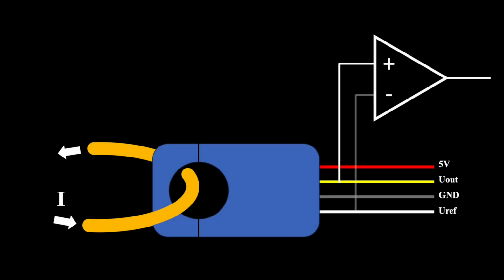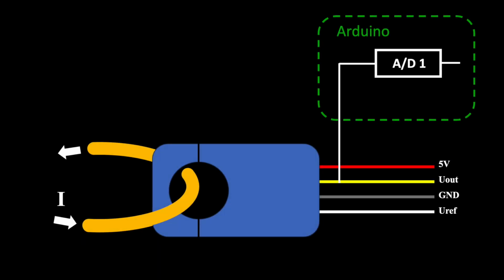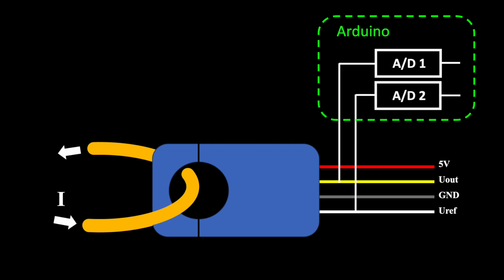Applying a differential measurement, we can eliminate the zero offset drift using the reference voltage output. In this way, we are getting rid of the 2.5 volt bias and the output is directly proportional to the measured current. The same principle applies with 2 AD converters instead of 1. In this case, the difference is computed in the processor code.